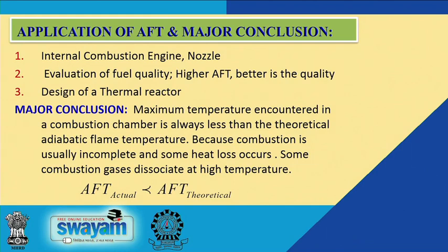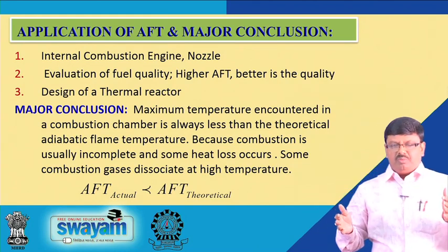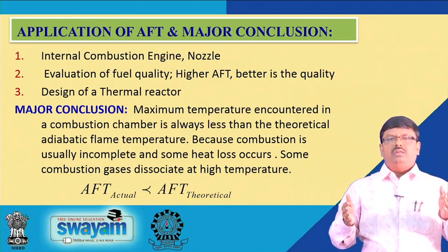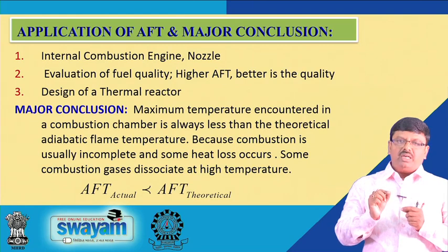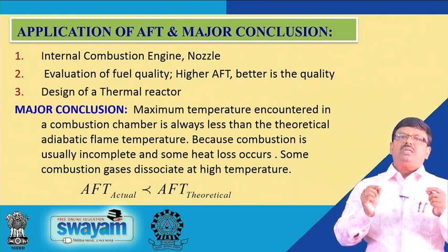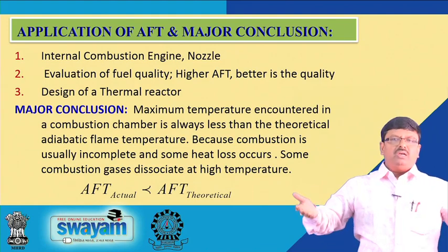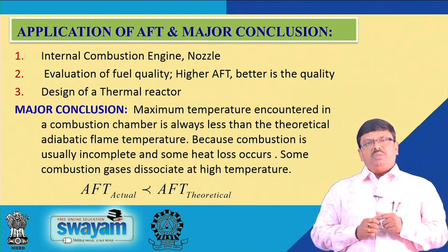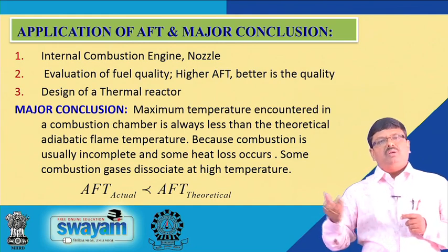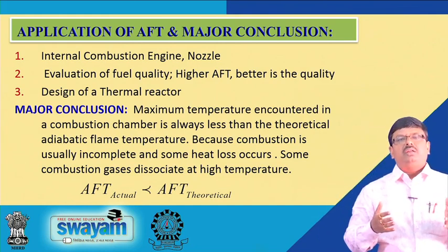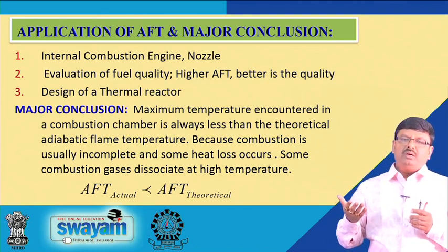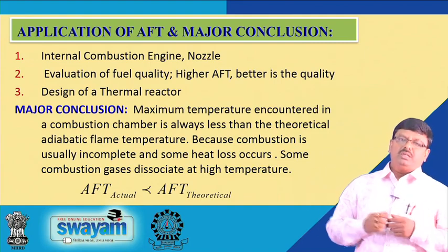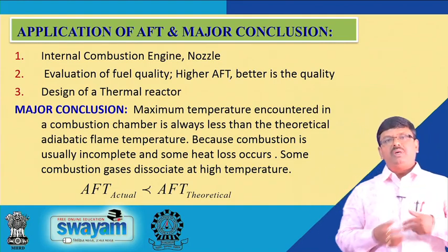Design of a thermal reactor. We chemical engineers need to consider the design of a thermal reactor for the chemical reaction engineering laboratory and the energy laboratory. This thermal reactor necessarily consists of different layers. If we consider just a muffle furnace, it necessarily consists of 3 different layers: the innermost layer, the intermediate layer and the outermost layer. These 3 layers are made of different materials, and they serve 3 different purposes.